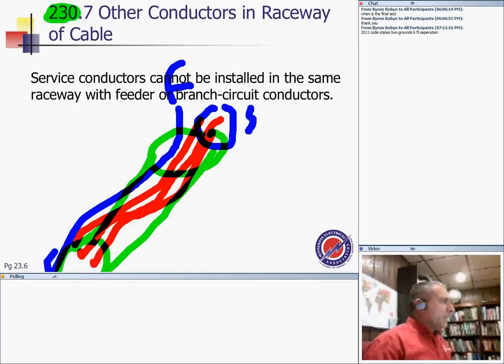So this way with feeder or branch circuit. The conduit or cable that contains the service conductors are sacred cows and shall not be used to house the feeder or branch circuits. So that's a no-no. Any question about this, guys?